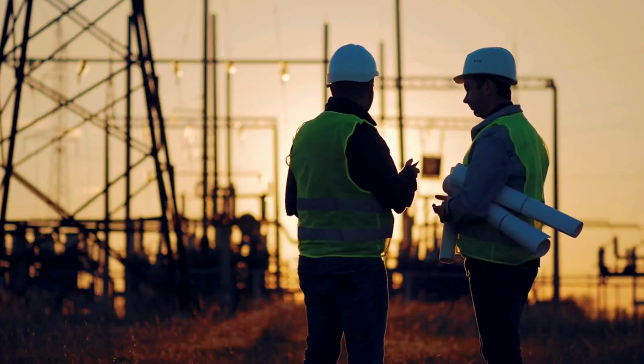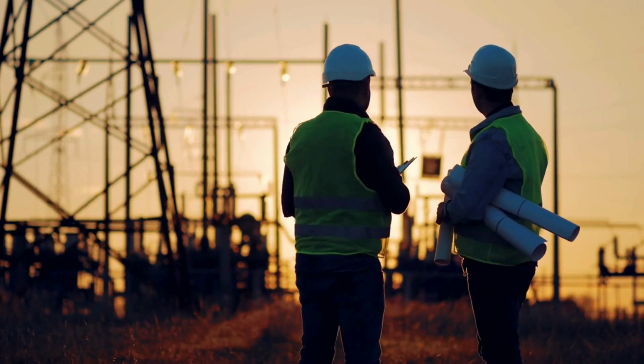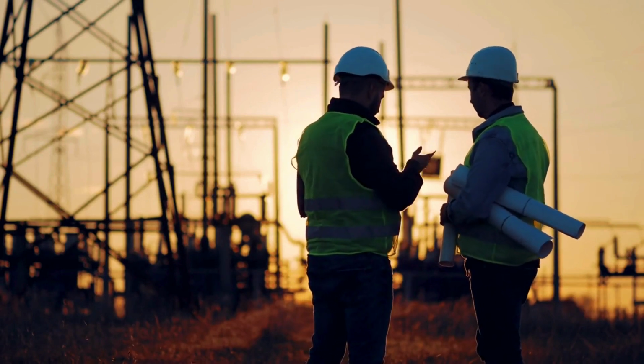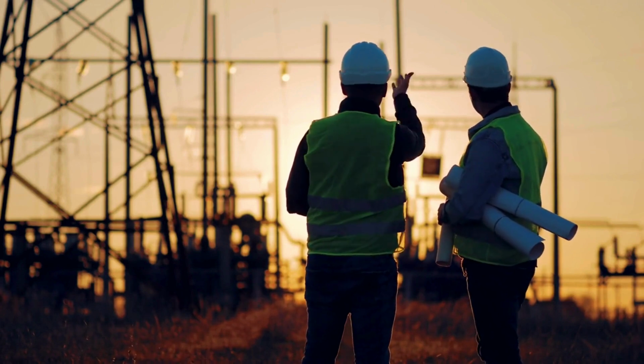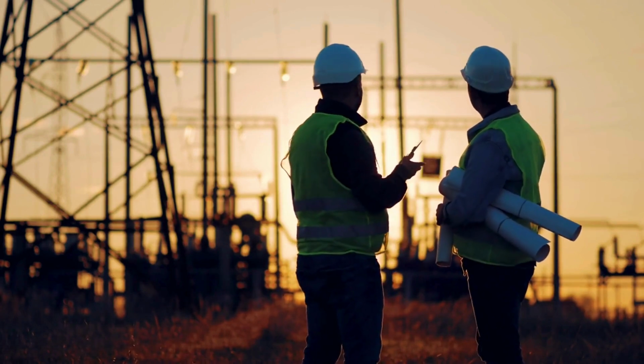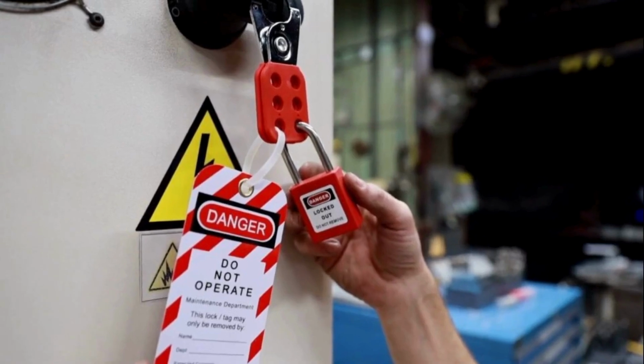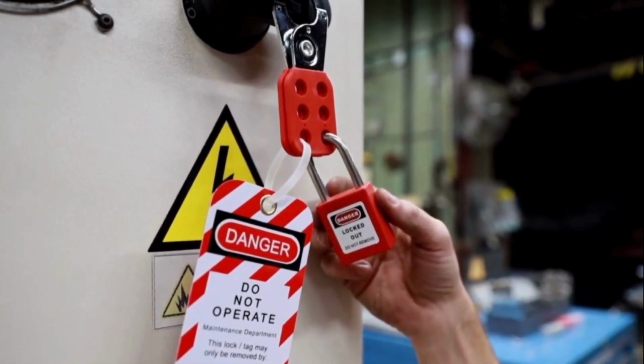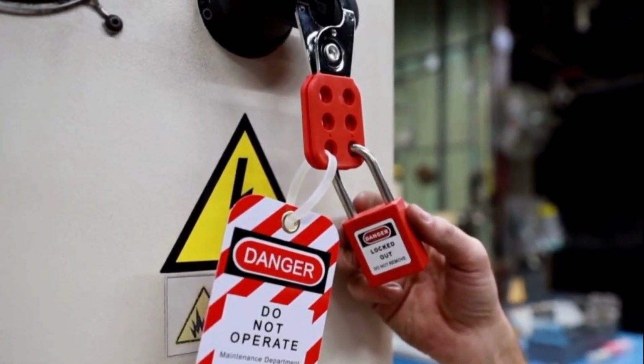The proper procedure is to wait. Most equipment manufacturers specify a discharge time, usually 5 to 30 minutes depending on the capacitor size and discharge resistor values. You lock out the equipment, you test it, and then you wait the specified time before you touch anything.